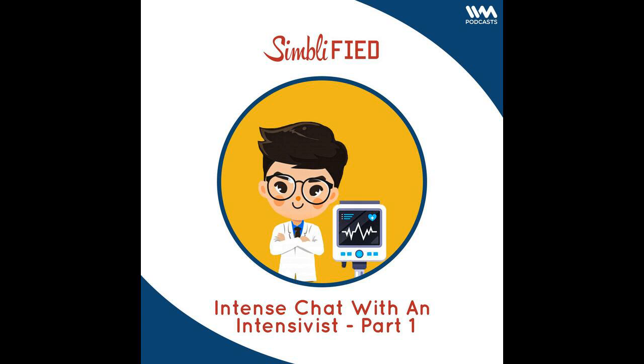Once you get above 24%, that becomes essentially a flammable mix, and one spark will ignite it. Just that small difference means 21 to 24 becomes a hazard. 24 is the limit imposed by the UK Fire Service, even though some papers say you have to get up to about 26. But it doesn't matter, it's not that big a change.